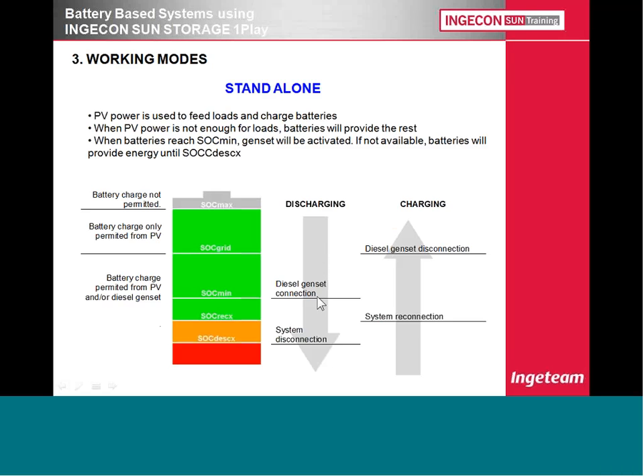what we want to do is keep the batteries fully charged to the maximum point as much as we can. So when the blackout comes, or the grid outage comes, when there's a grid drop, then we have enough power in the battery to actually feed our loads, okay? So as you can see, the strategy is different. Basically, you keep your batteries fully charged, and when the grid drops, then they start discharging, and they drop down to this value here. So when you size your system, you have to make sure that the size of your batteries is enough to actually feed the loads for the period of time required. You need to know how much your loads are, or how long the grid drop or the grid blackout is going to last. So you size your batteries taking those values into consideration.